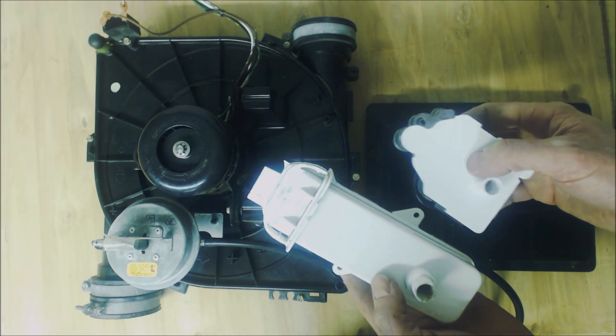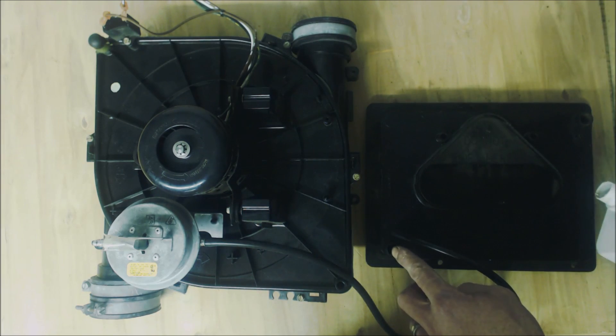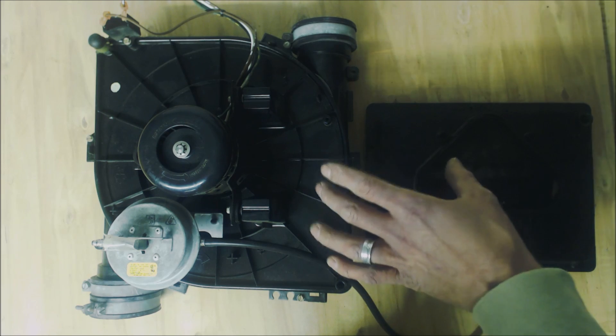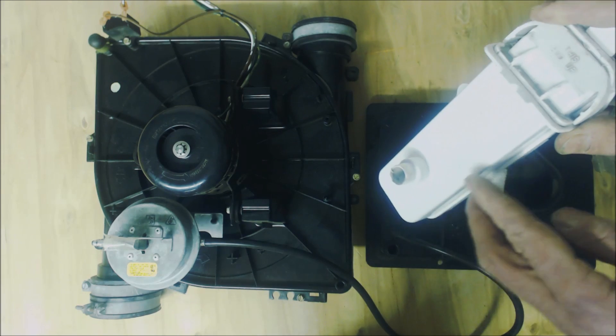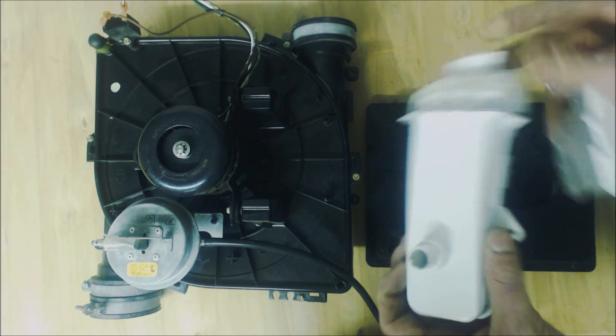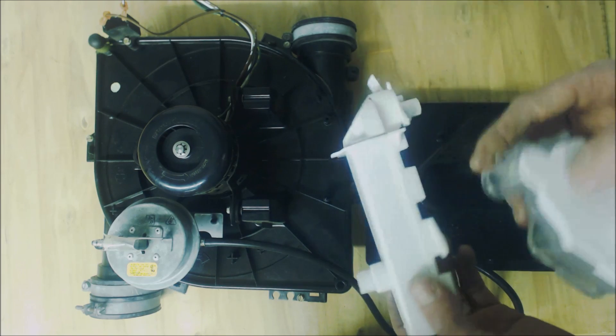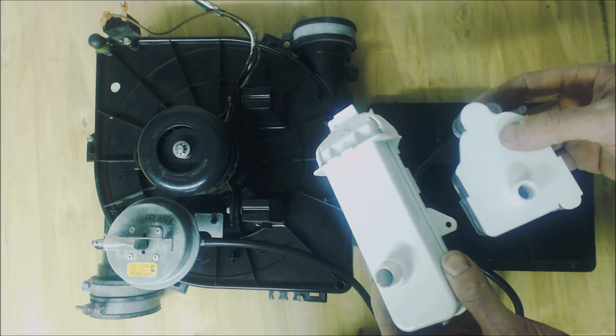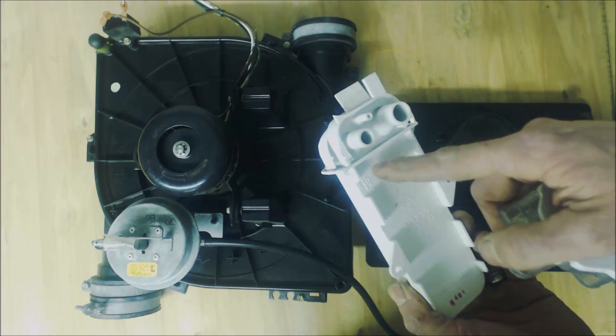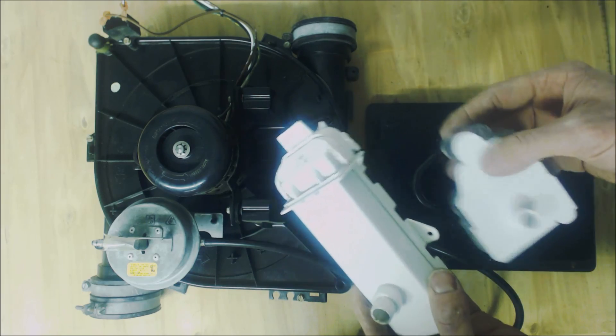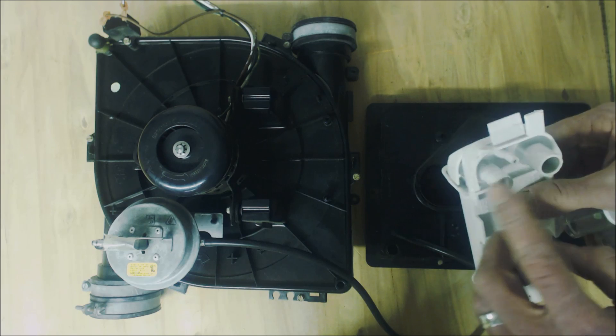You want to make sure you also have a trap right here installed. So this water won't be able to drain out of the furnace in a negative pressure zone unless you have water weight in a trap. So that's what the point of having these traps are. Now by the pure fact of having a trap means that over time the water can be stagnant inside and end up clogging up. So you want to go ahead and clean these out.